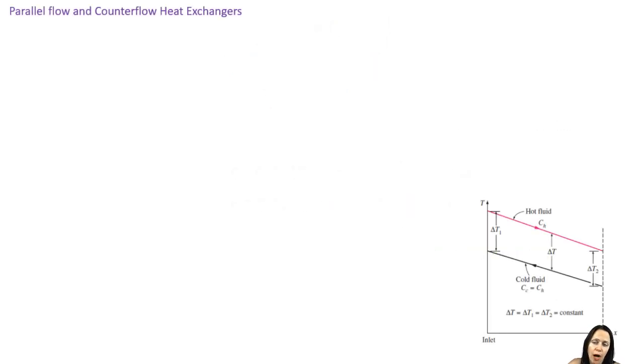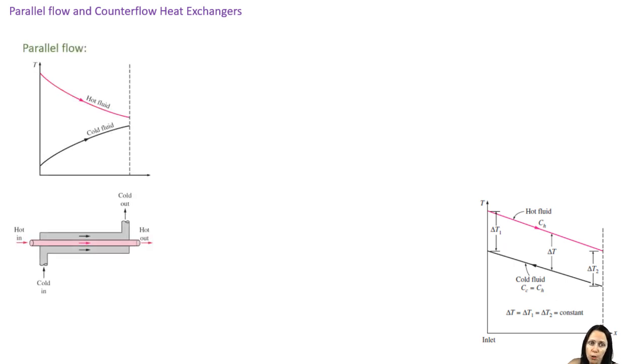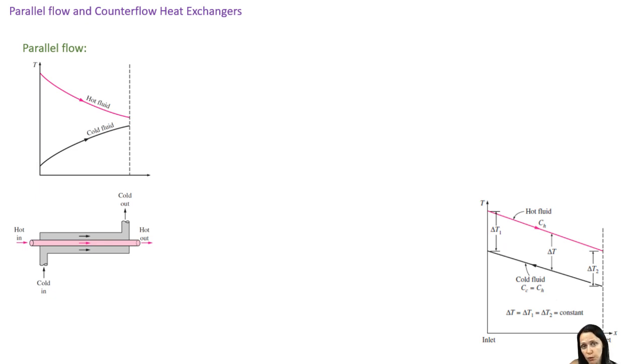Now let's look at some general concepts for parallel and counter flow heat exchangers. In a parallel flow heat exchanger, the hot and cold streams enter at the same end. This results in the highest heat transfer rate due to the highest temperature difference between the two fluids at the inlet. As the fluids flow through, the hot fluid cools off, the cold fluid heats up, and they come closer to the same temperature at the outlet.